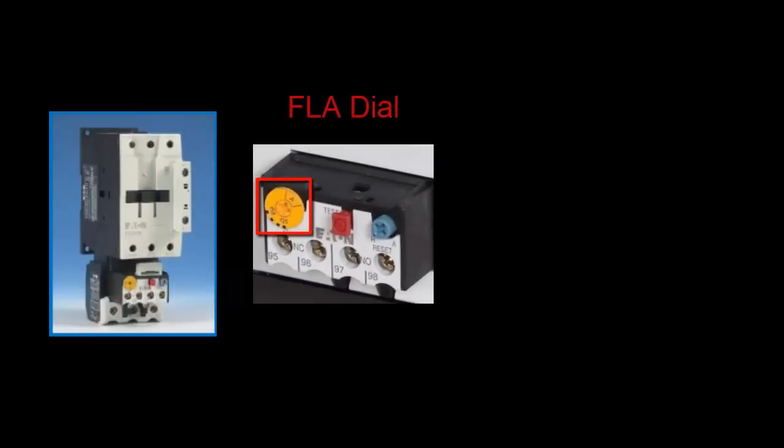So when the contactor is energized, you have power coming in from the line side, flowing all the way through the load side of the overload relay. On the face of the relay, you have the FLA dial, where you set the rated FLA or full load amps of the motor.